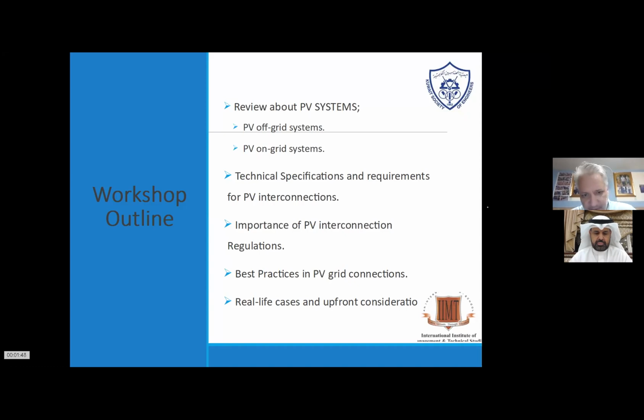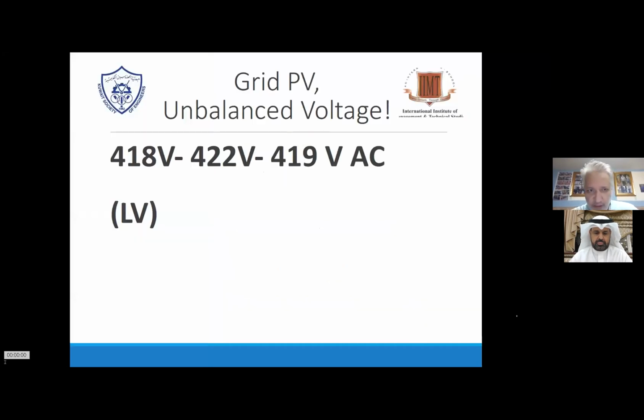And so you have these best practices, and let's see when we dive into this. For example, when you have a system set up and you do the commissioning, you should write down the phases, whether they are balanced or not. In this example, it's a little bit unbalanced already, so we are not feeding in, and we can already see 418, 422, and 419. That's mostly the low voltage side, which is already a little bit uneven. And of course, we are dealing with the transformers, which give the phases 10 or 20 kilovolt.